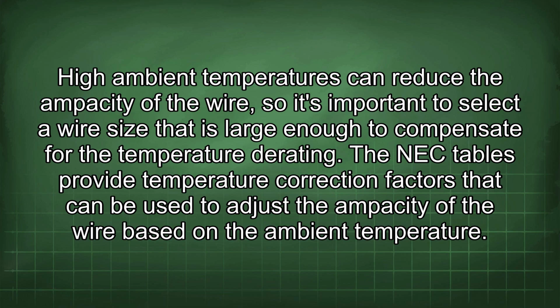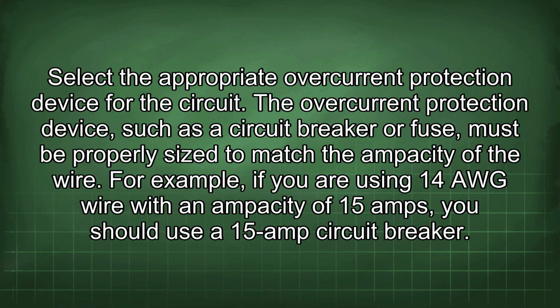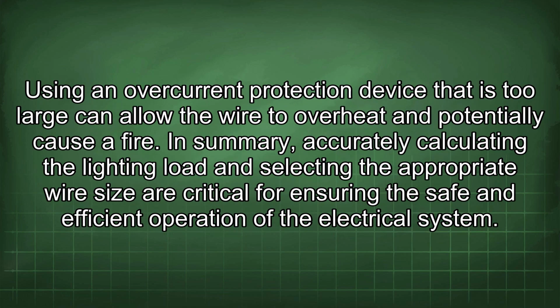Select the appropriate overcurrent protection device for the circuit. The overcurrent protection device, such as a circuit breaker or fuse, must be properly sized to match the ampacity of the wire. For example, if you are using 14 AWG wire with an ampacity of 15 amps, you should use a 15 amp circuit breaker. Using an overcurrent protection device that is too large can allow the wire to overheat and potentially cause a fire.